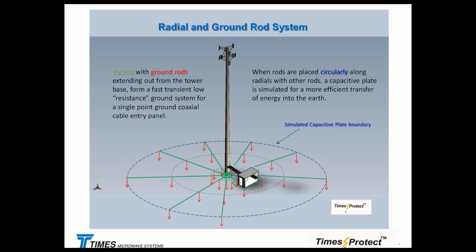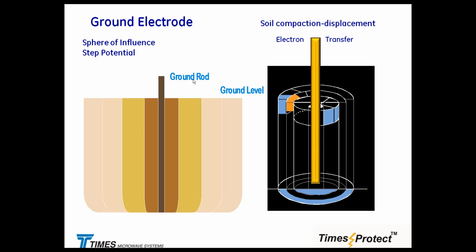You might drive one ground rod, hit the water table, basically, and you're going to measure half an ohm. Well, that's great AC or DC ground, but when you take a look at the dissipation capability of a rod like that, it's not going to help us very much in a lightning event. The most basic grounding material will be a grounding rod, and as you see, the most effective will be just the surroundings of the grounding rod, where you're going to be shunting the energy basically to the clumps of soil.